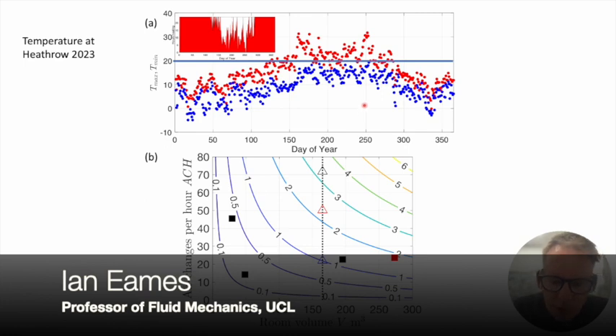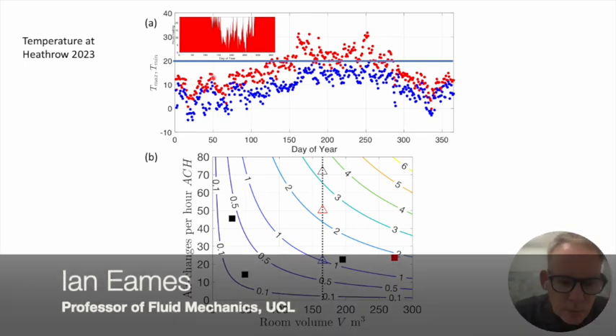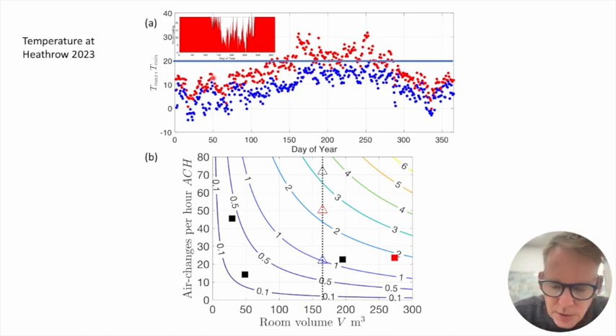The challenge, obviously, for the mechanical engineering system is that the air comes in at a temperature generally much lower than the temperature you require it at, which is about 20 degrees, 21 degrees, depending on what surgery you're doing. And that increase in temperature must be achieved through heating, either through gas or electricity. The ACH, the air change per hour, typically for the room is probably about 25, giving about 1.2 cubic meters per second for the theatre.